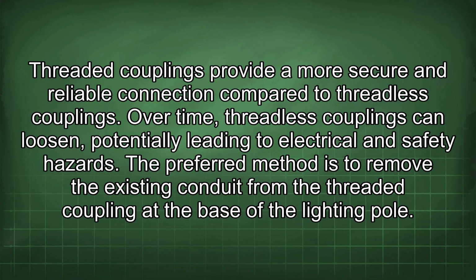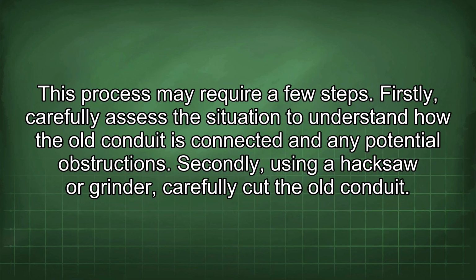Threaded couplings provide a more secure and reliable connection compared to threadless couplings. Over time, threadless couplings can loosen, potentially leading to electrical and safety hazards. The preferred method is to remove the existing conduit from the threaded coupling at the base of the lighting pole. This process may require a few steps.